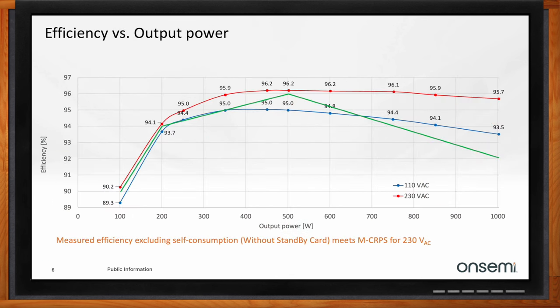In the 1 kilowatt example, the battery voltage is 48 volts. The efficiency is measured between 100 watts and 1 kilowatt. You can see the red line, which shows 230 volts, the European mains, or line to line for the US market, where you will see around 96% efficiency on average. When you go to 110 volts AC or 120 volts AC, your input PFC losses are a little higher. Because of that, your efficiency will be around 95% at 50% load. And then at 1 kilowatt, the efficiency will be a little lower.